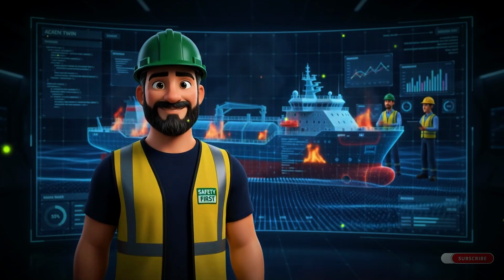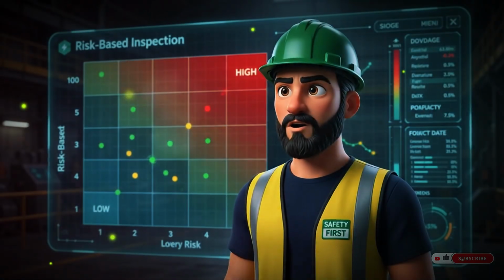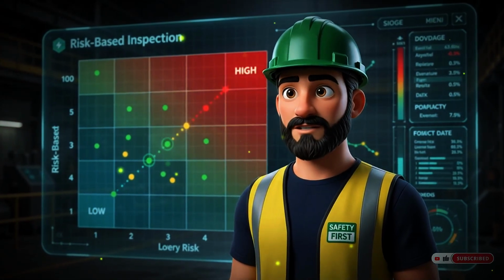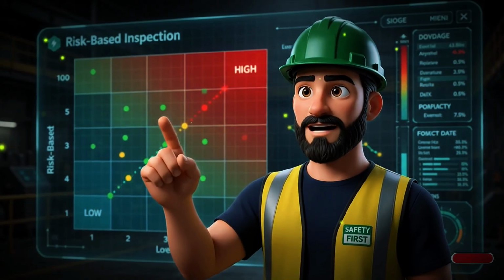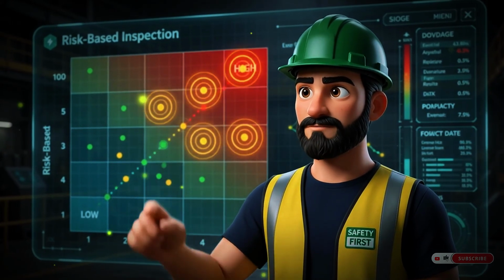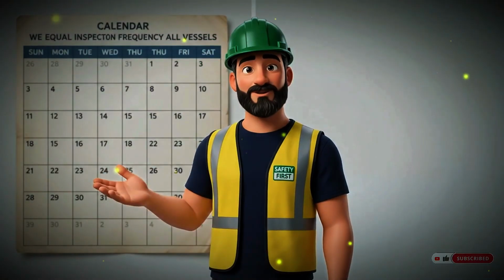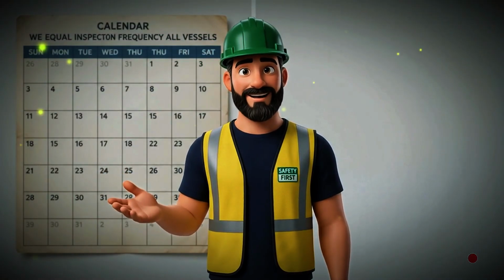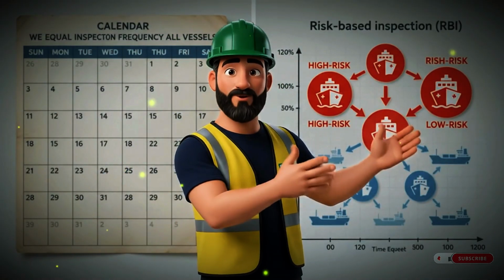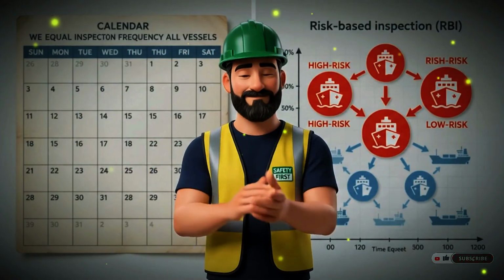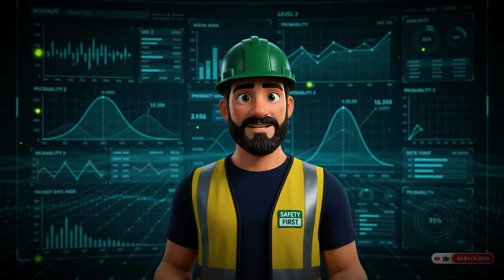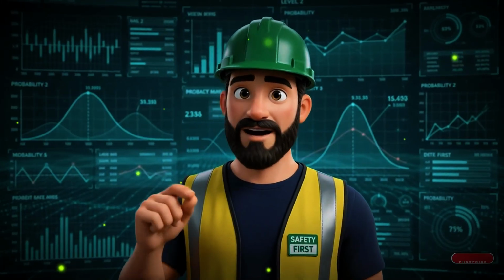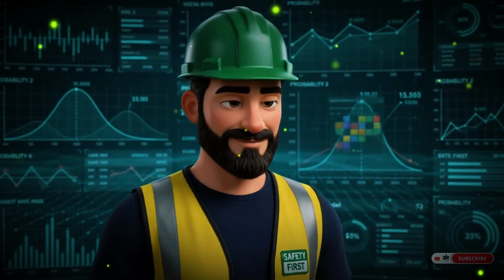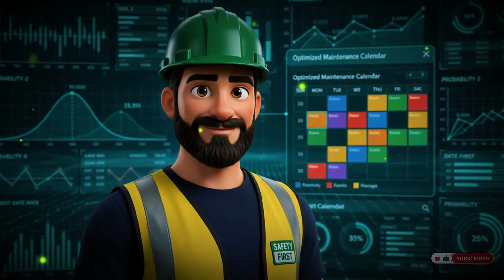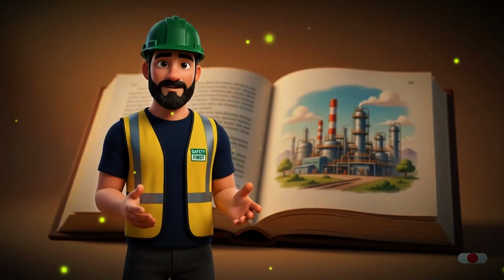And risk-based inspection, RBI, governed by API 580 and API 581, has fundamentally changed how industries plan their maintenance activities. Instead of inspecting all equipment with the same frequency, RBI concentrates inspection resources on the equipment with the highest probability of failure and the highest consequence of failure. More attention where the risk is greatest. Less waste where the risk is low. It is data-driven safety engineering, not intuition.